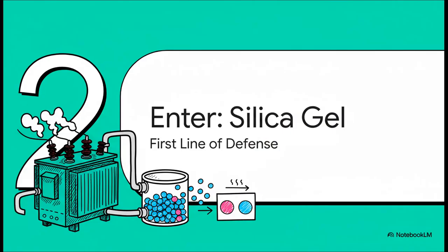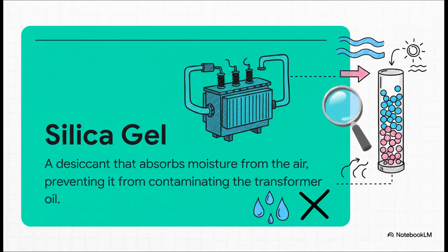Okay, so that brings us to our next part, the moisture-fighting guardian. To let the transformer breathe safely, without poisoning itself with moisture, it needs a filter. And this is where our hero comes in. This is its first line of defense, the silica gel breather. And the solution is beautifully simple. Silica gel is what we call a desiccant. Basically, it's a material that is incredibly thirsty for water. You can picture it like a microscopic sponge. So as that moist air gets pulled in, the gel just snatches the water molecules right out of it and only lets clean, dry air get through to the transformer.